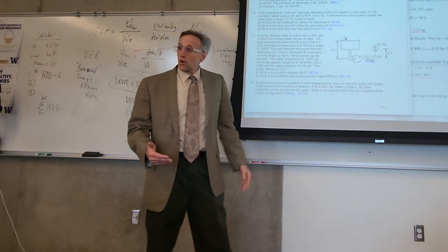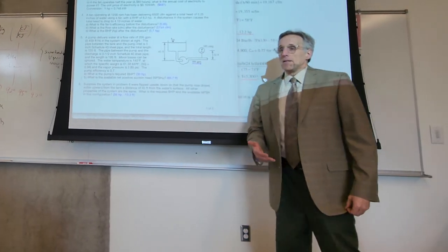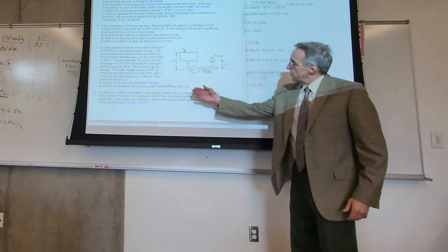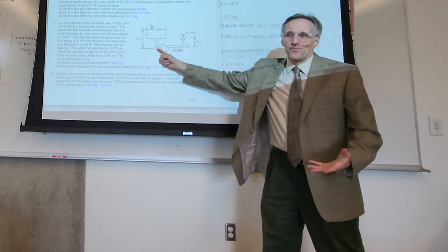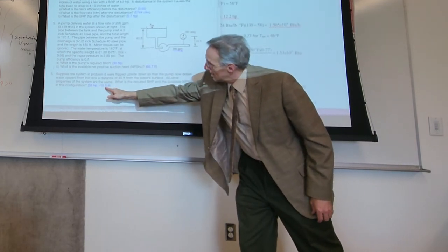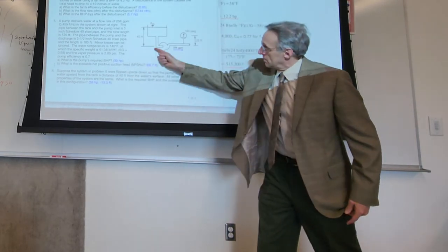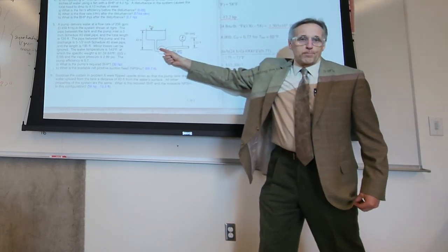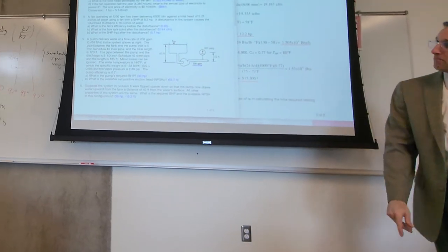That's when you have to be careful, because you can get into problems with having a negative net positive suction head and ending up with water vapor instead of liquid. And that's actually what happens here. You see the net positive suction head negative 13.3 means that you're going to be trying to pump water vapor instead of liquid. And you definitely don't want to do that.